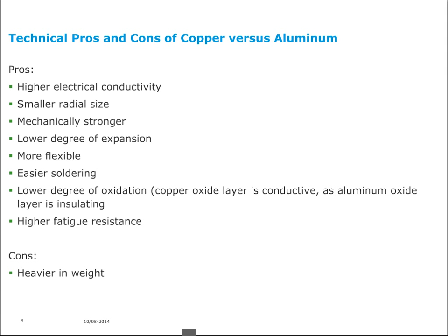Let's now say a few words. We have not that much time, but let's say a few words about failure mechanisms in which the material of the conductor plays a role. We start with aluminum. There is in the literature information given about the chemical reaction between water and aluminum. When water enters the conductor, then you get aluminum oxide and hydrogen. Hydrogen is developed in that process, and that can be at relatively high pressures, damaging joint structures and resulting finally into failure.